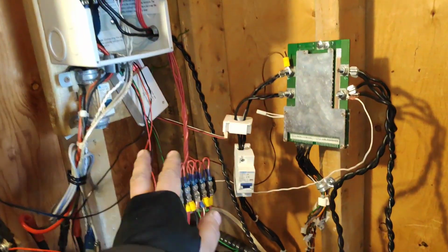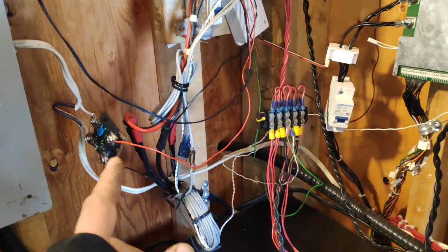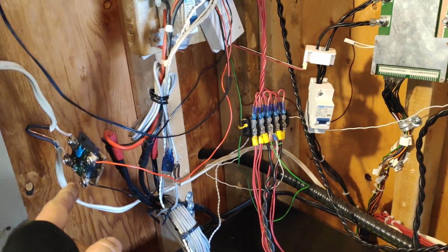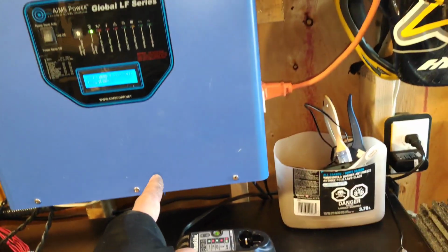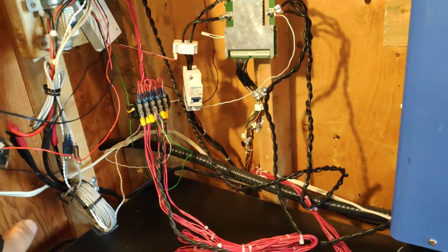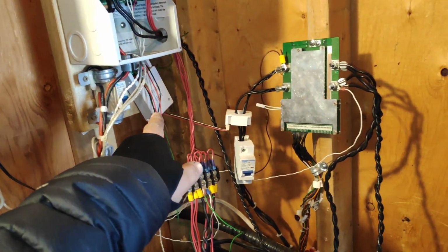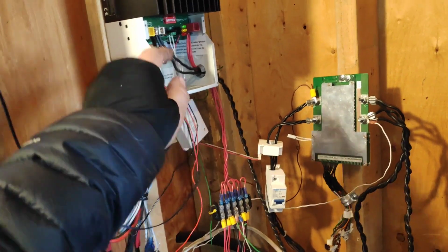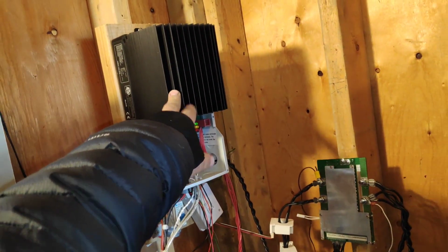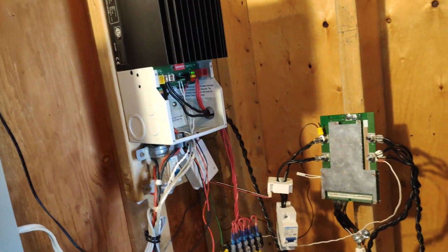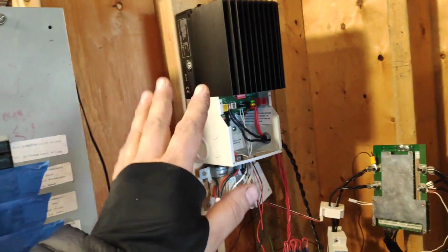The device, essentially, you can program so if the battery goes too low, it automatically kicks on the onboard charger from the inverter, which feeds directly to the battery. Then at the program setting of the voltage, even though I've got this programmed for 48.89 volts, I have the charger set to about 50.2 or 50.3 or so.